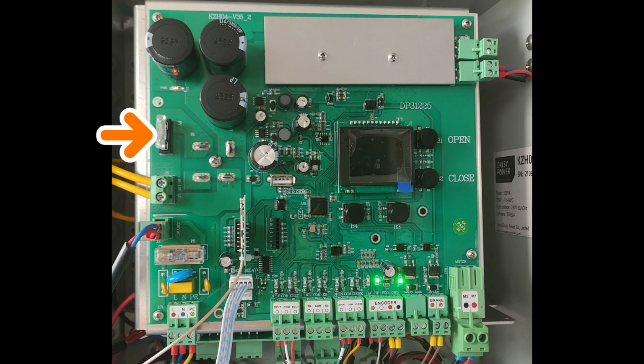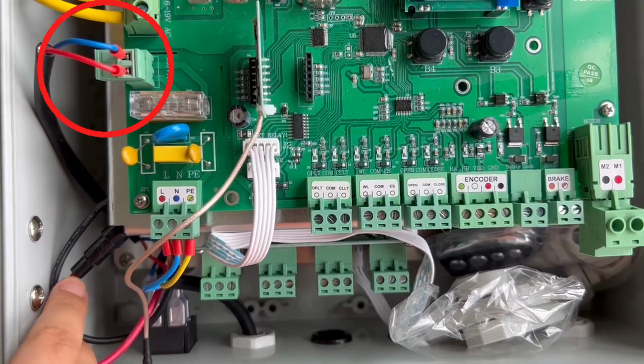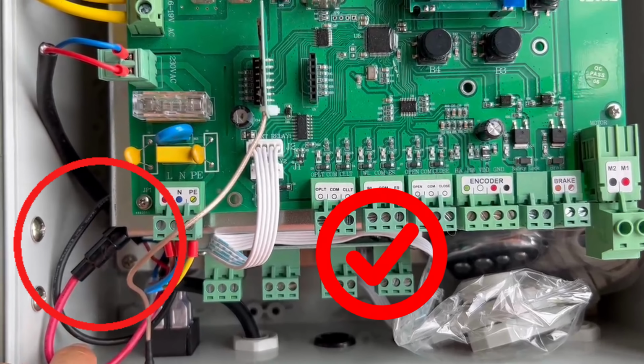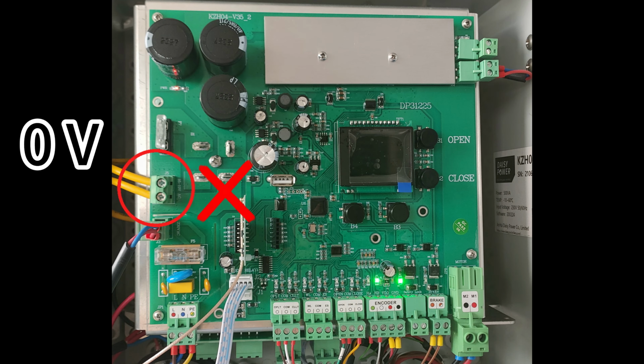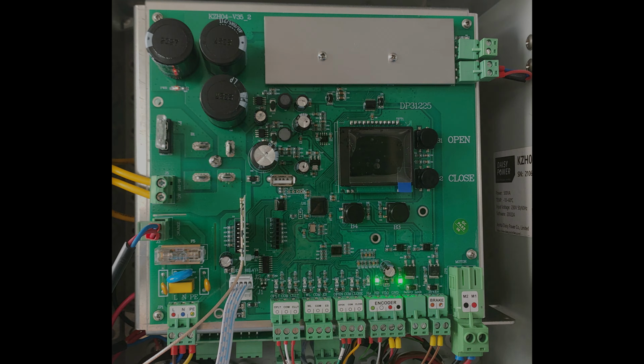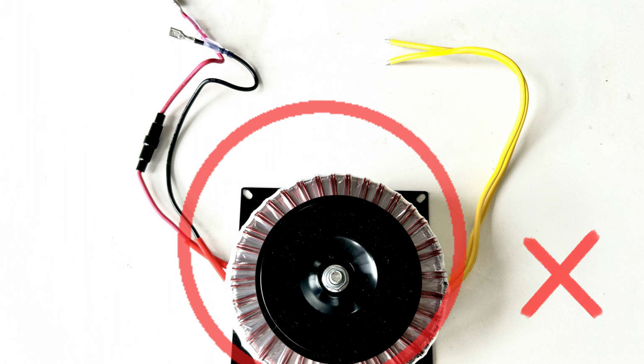We followed the same steps for voltage checking. It turned out the transformer input was okay, the transformer fuse was okay, while the output was not. All the information showed the transformer coil was damaged. The client replaced it with a new control box. Problem solved.